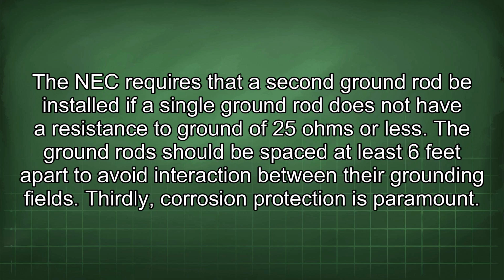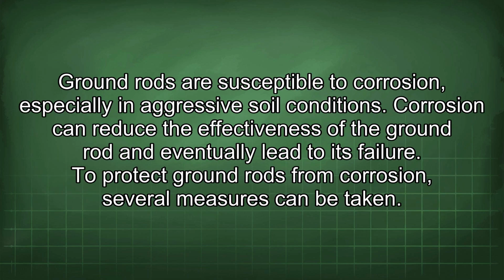Thirdly, corrosion protection is paramount. Ground rods are susceptible to corrosion, especially in aggressive soil conditions. Corrosion can reduce the effectiveness of the ground rod and eventually lead to its failure. To protect ground rods from corrosion, several measures can be taken.